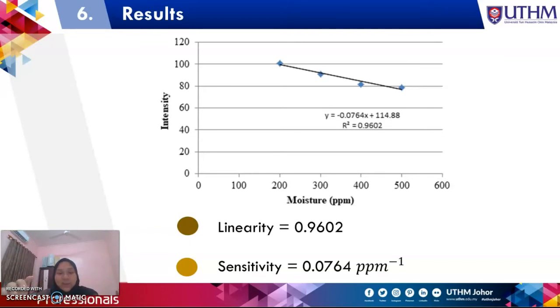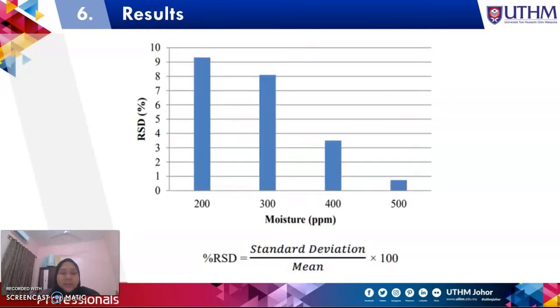The linearity is 0.9602 and the sensitivity is 0.0764 per ppm. And this is our RSD percentage. In this research, for every different moisture content, we run the testing 3 times, and by using the 3 different outputs for each moisture content in the transformer oil, we can calculate the percentage of RSD using this formula. So this is a graph of the percentage RSD for 200 ppm, 300 ppm, 400 ppm, and 500 ppm.